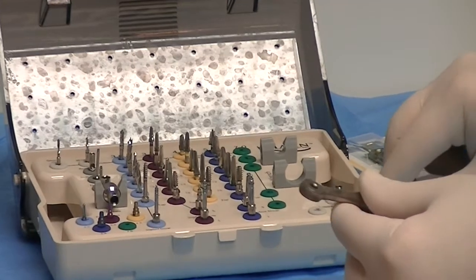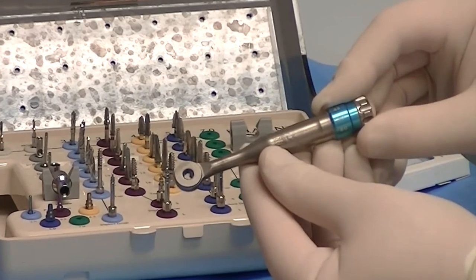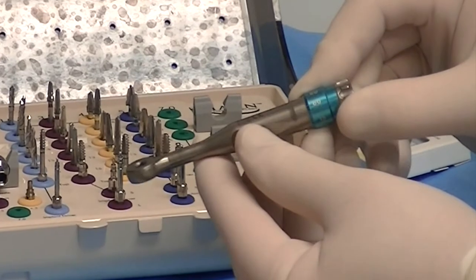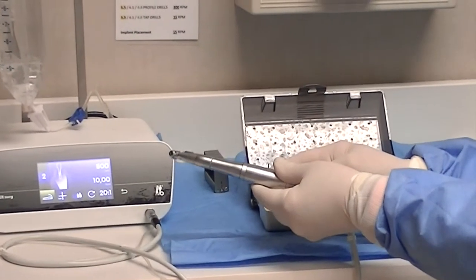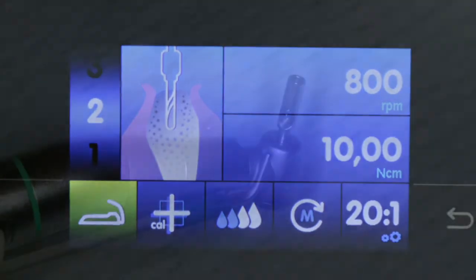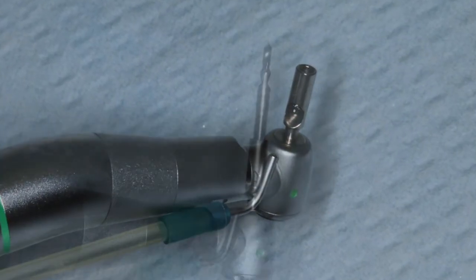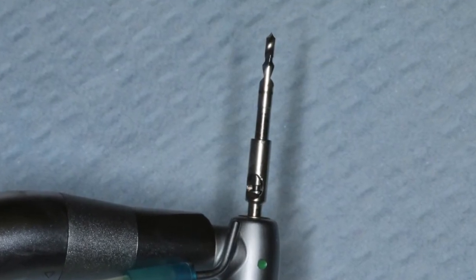We have a single-handle torque wrench which will measure the amount of torque that we will use in a certain situation. Here we're using a handpiece — in this system we're going to drill at 800 RPMs at 10 Ncm. Here's a drill extension that will allow us to make our initial penetration using a 2.4 diameter burr.